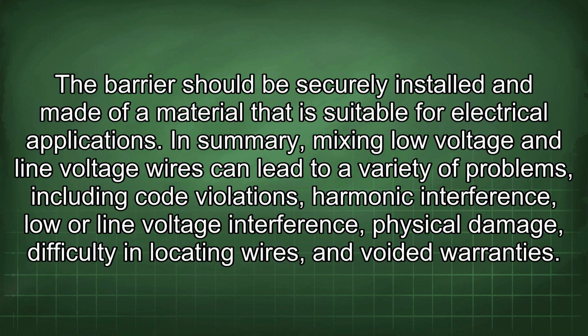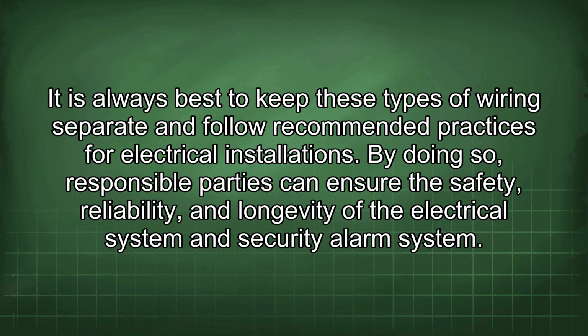In summary, mixing low voltage and line voltage wires can lead to a variety of problems, including code violations, harmonic interference, low or line voltage interference, physical damage, difficulty in locating wires, and voided warranties. It is always best to keep these types of wiring separate and follow recommended practices for electrical installations. By doing so, responsible parties can ensure the safety, reliability, and longevity of the electrical system and security alarm system.